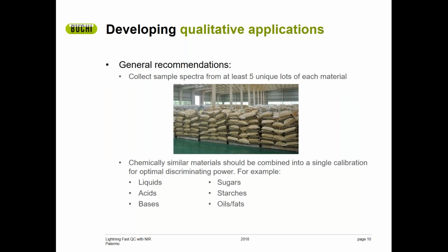Here are some general guidelines for developing qualitative applications. First, please consider that spectra and samples from at least 5 unique batches or lots of material should be collected for use in method development. Those lots should span as much of your anticipated sources of spectral variation as possible, whether that's multiple suppliers, variations in moisture content, particle size, or some other variable. Those lots will then be partitioned into either a calibration or validation set.